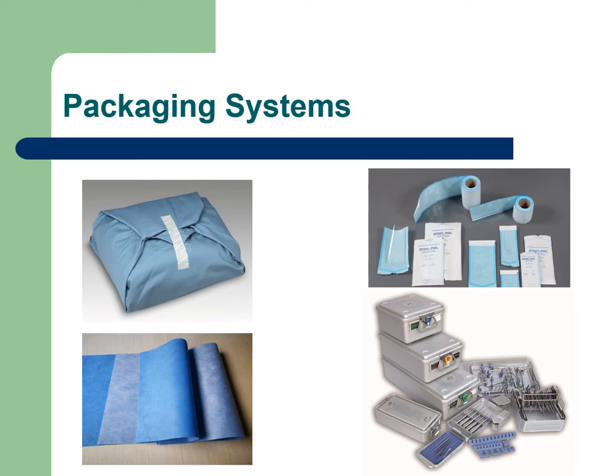Similar to drapes we talked about before, there are reusable cloth wrappers and also non-woven single-use materials. There are peel pouches and also rigid sterilization containers. On the top left you'll see the cloth wrapper. These woven wrappers are dense enough to protect the stuff inside but porous enough to allow penetration of steam or gas. They have a thread count of 140 per square inch, which they have to have to be effective.